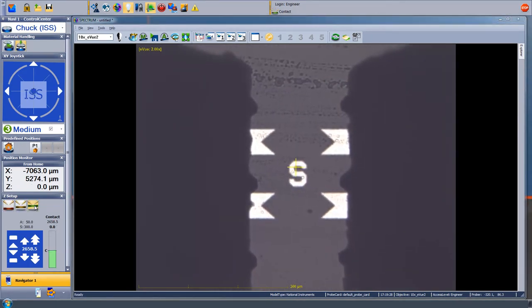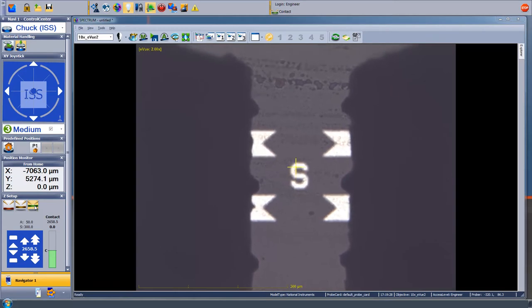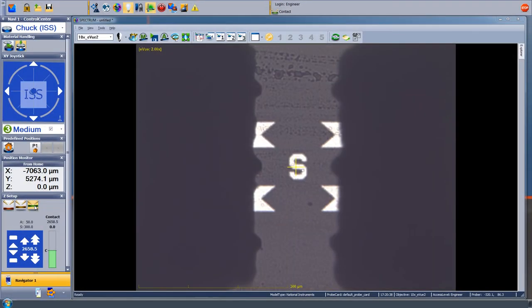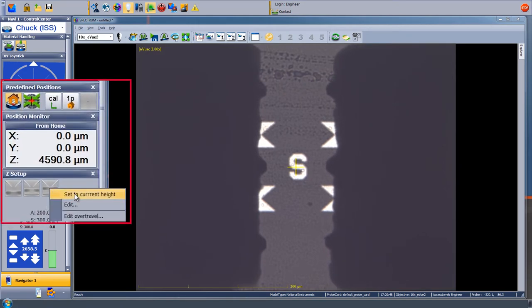The infinity probes we are using today work with a very light skate. The probe should be adjusted so that they make contact to the substrate at the apex of the V and then skate to the middle of the V at full contact position. You can see here we came very close, so I will go ahead and set this as the contact height.